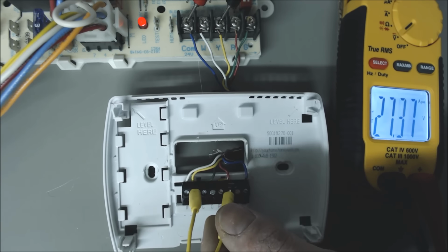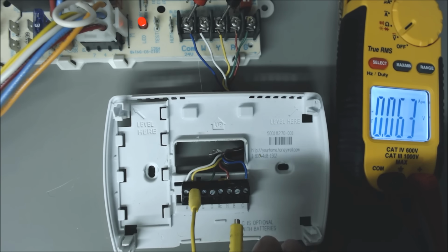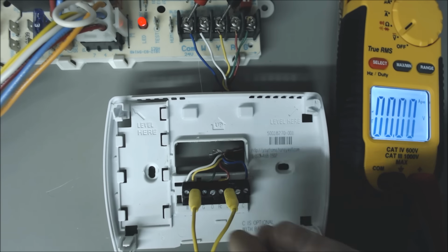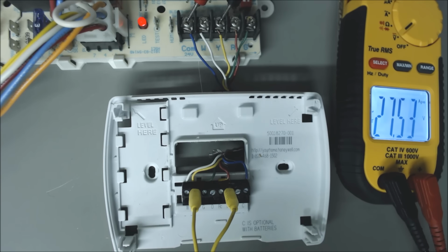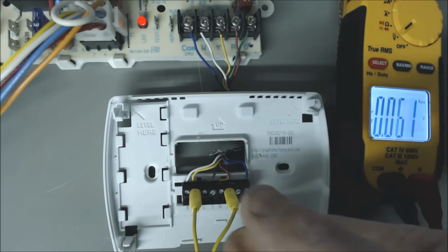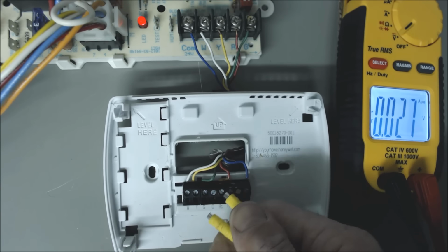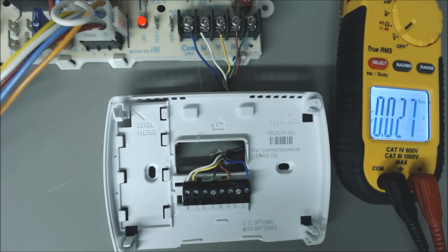If we take one magnet off of our lead right here, you see that we are not reading any voltage. And now with our mag jumpers right here, we are reading 27.5 volts. Okay, so that's how you do it. That's how you read voltage at the control board in order to verify that the thermostat wire is good and the thermostat face is good.